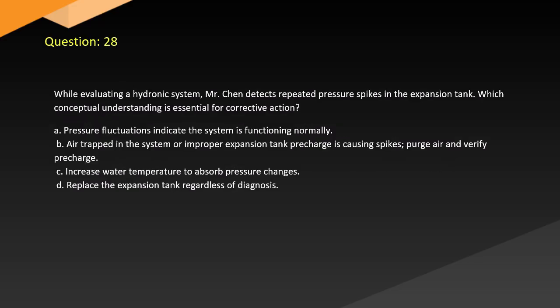Question 28. While evaluating a hydronic system, Mr. Chen detects repeated pressure spikes in the expansion tank. Which conceptual understanding is essential for corrective action? A. Pressure fluctuations indicate the system is functioning normally. B. Air trapped in the system or improper expansion tank precharge causing spikes. Purge air and verify precharge. C. Increase water temperature to absorb pressure changes. D. Replace the expansion tank regardless of diagnosis.